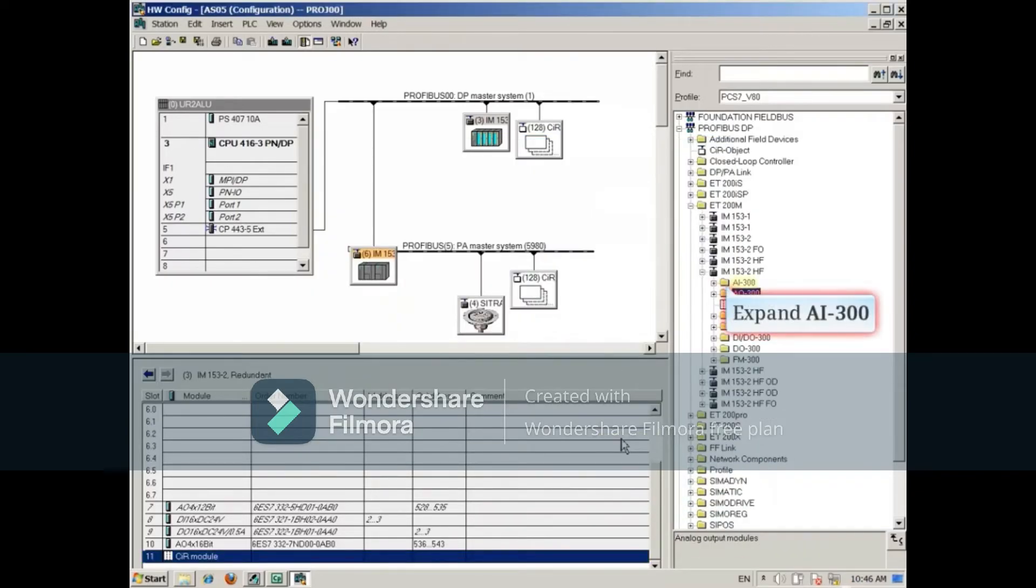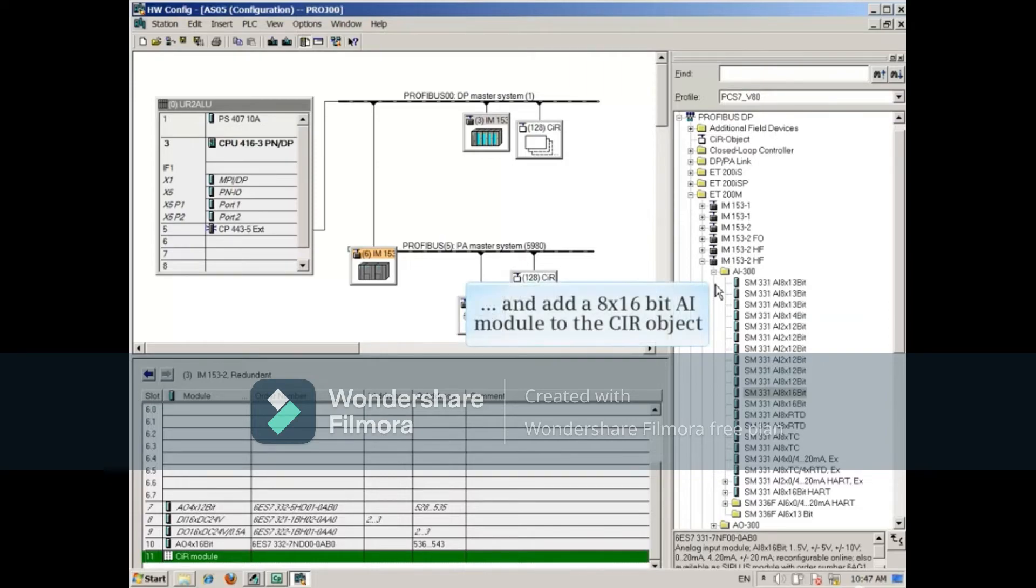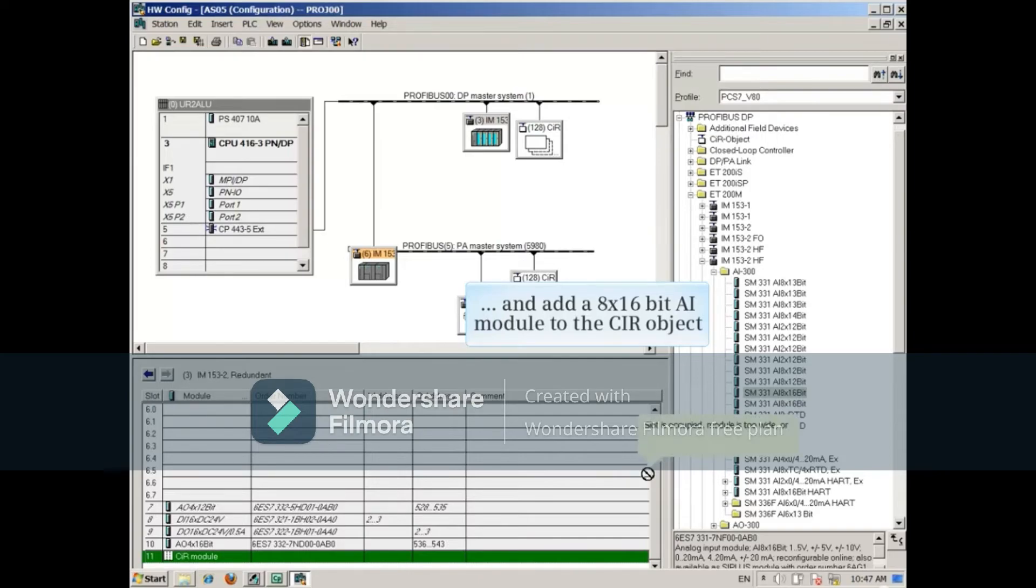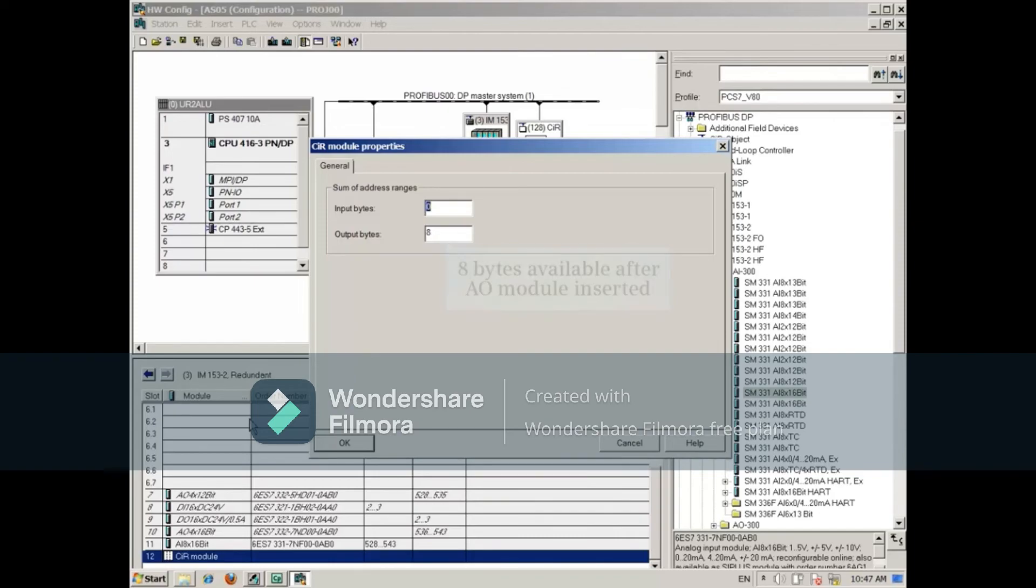Expand the AI list and add an 8 times 16-bit AI module to the CIR object. Once again, open the CIR properties to see that the whole 16 bytes of memory has been consumed for the 8 times 16-bit, 2-byte module. Close the CIR properties.